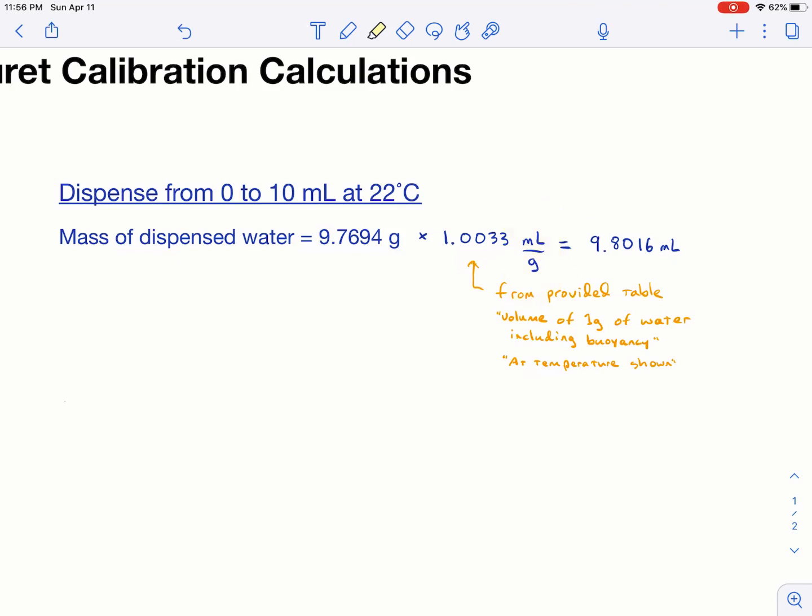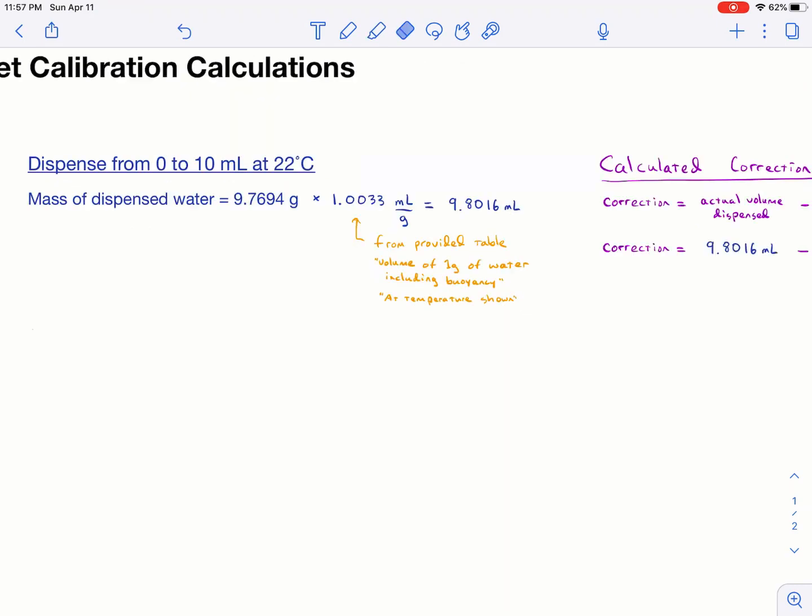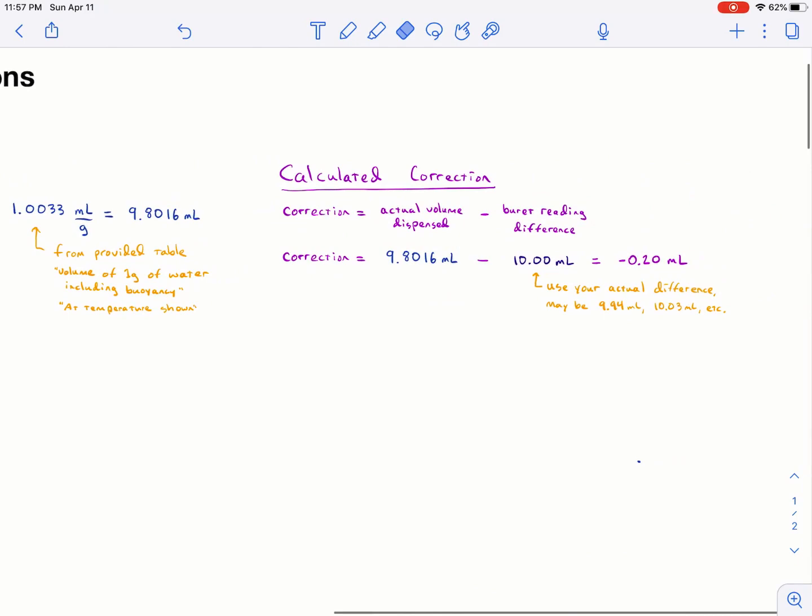And then this is the volume of water that you actually dispensed at this temperature when you went from zero to 10 mils. And to calculate the correction from that, you need to take the actual volume dispense and subtract the burette reading difference from it. And that's the order. You want actual minus what it should have been. Because that way, if you dispense less than you think you did, you get a negative correction. If you dispense more than you thought you should have, then you get a positive correction. And that kind of makes sense.